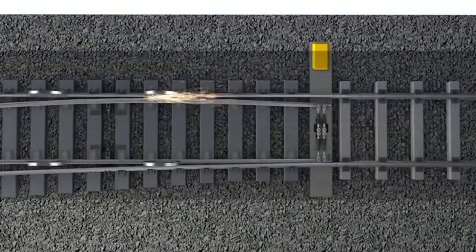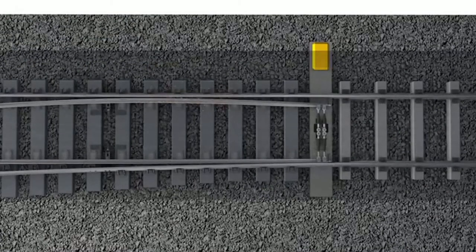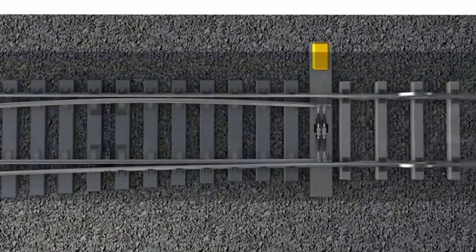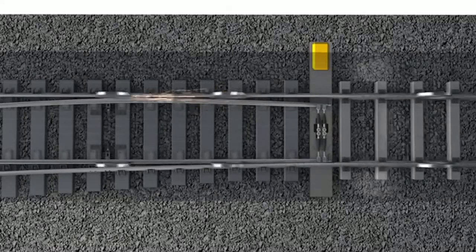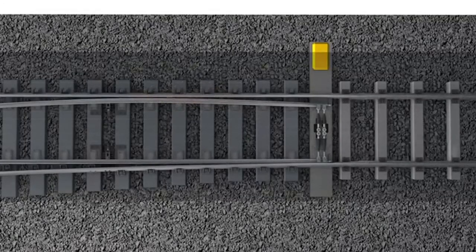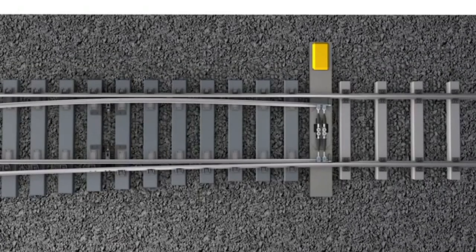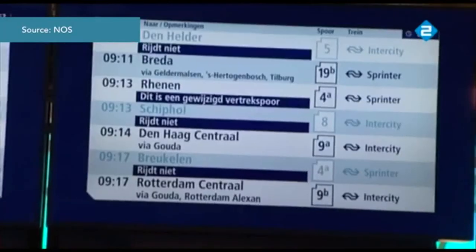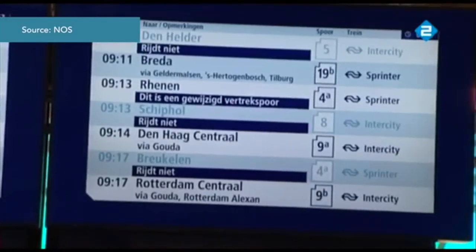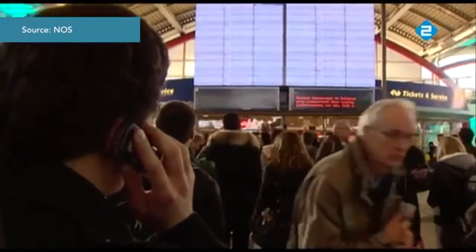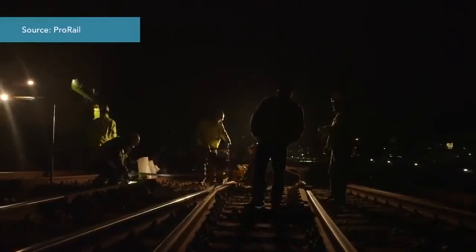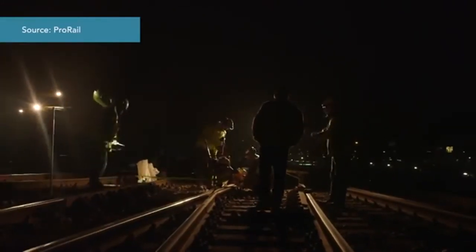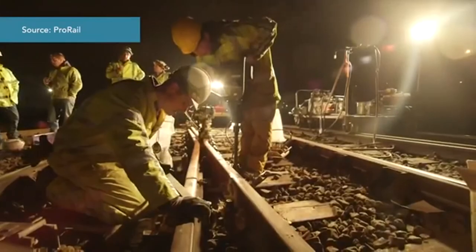Instead, the maintenance regulations imposed on contractors by ProRail were insufficient to prevent flangeback contacts. In this respect, the Dutch Safety Board notes that maintenance, more strongly than in the past, focuses on preventing train disruptions. Because the wear of the switch parts supporting the blades and subsequent flangeback contacts did not lead to such disruptions, insufficient attention was paid to these parts in maintenance.